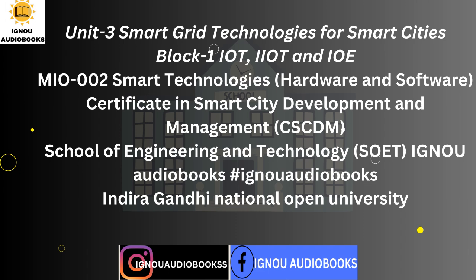In contrast to conventional SCADA systems where RTUs are used to acquire voltage, current and frequency, wide area monitoring systems acquire current, voltage, both magnitude and phase angle, and frequency measurements via phasor measurement units, PMUs. These are time synchronized via GPS receivers to a resolution of 1 microsecond, enabling real-time dynamic state measurement and monitoring across the widely spread grid. Since WAMS information is time synchronized, it also provides opportunity to control and protect systems based on wide area signals.